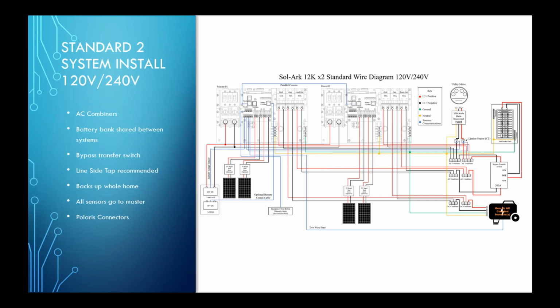But please keep in mind, obviously, the project dictates the number of units. If it is greater or if their usage is greater, then we do recommend doing some sort of critical loads panel. But really, the only things different between a single and a double is the AC inputs are paralleled, and the battery bank itself is paralleled to both units. They will each have their own independent MPPTs, so you can land up to, in this case, 8 physical strings into the inverter itself. So it does give you a lot of capabilities for expansion and a lot of power in terms of DC. So yeah, that's basically the two system setup.